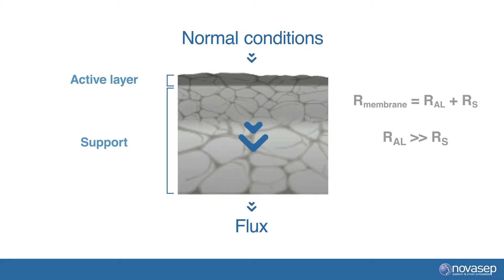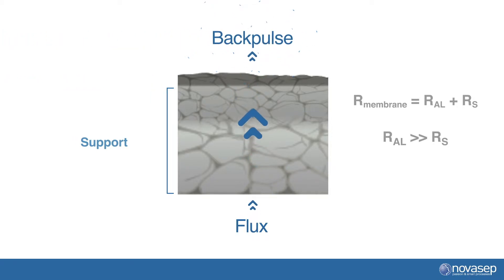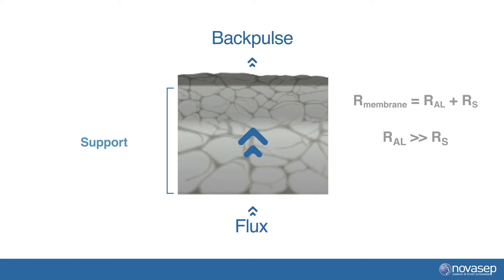For this reason, the active layer is kept as thin as possible. In normal conditions, flow first passes through this dense active layer and then easily flows through the support. During a back pulse it is the opposite. If the back pulse is not used properly, you can damage the bonding between the active layer and the support layer.